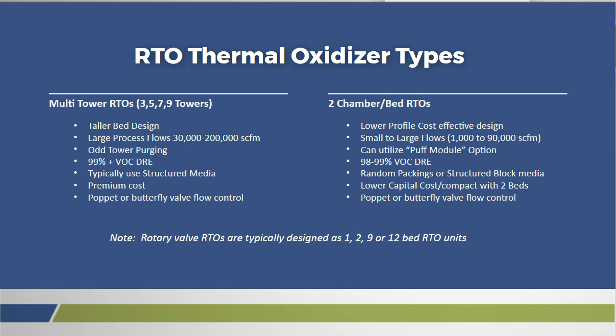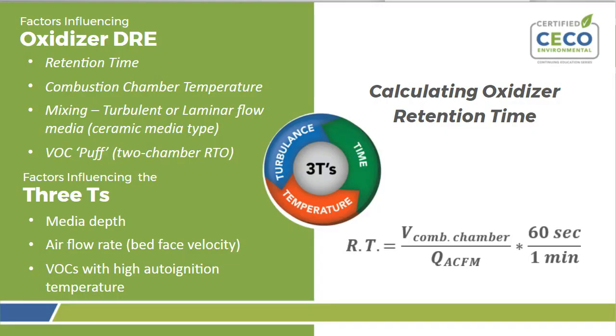So in the interest of time, keep moving forward here. Again, just reviewing factors that influence destruction efficiency, we have the 3 T's: retention time, temperature, and turbulence. But additionally, I added here the VOC puff, particularly for the 2-chamber. A quick retention time calc is just the volume in the combustion chamber divided by the actual flow rate through the combustion chamber at that high temperature.